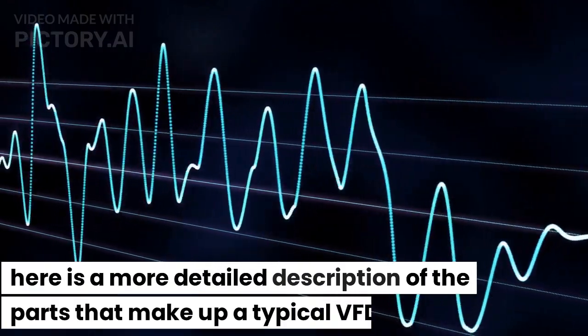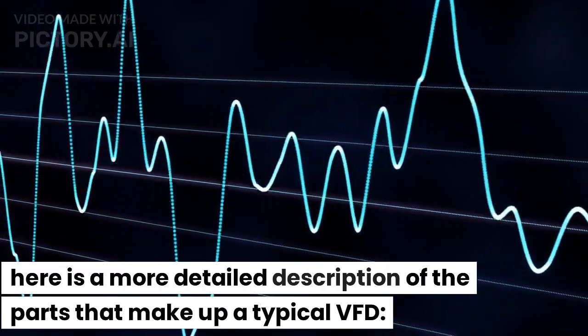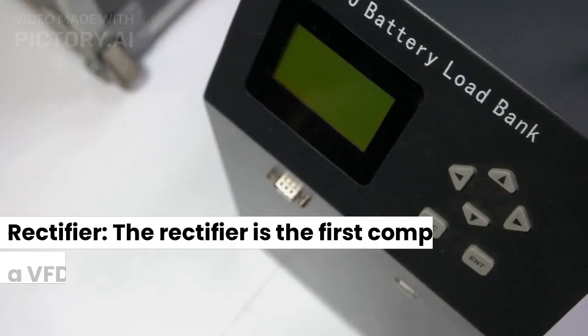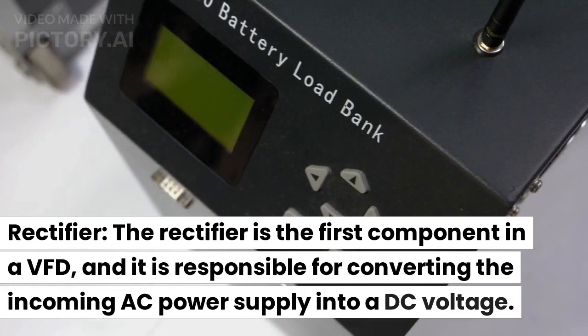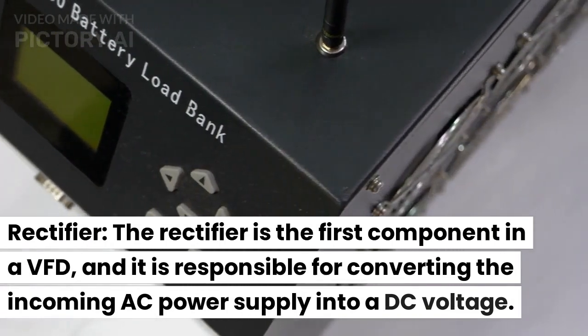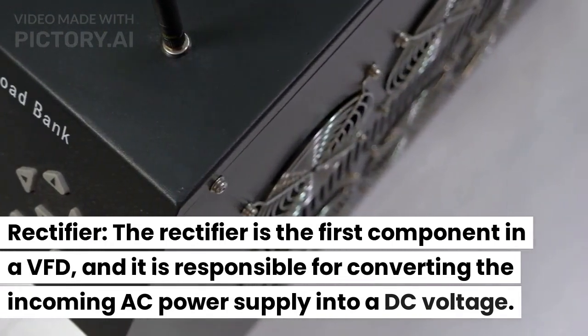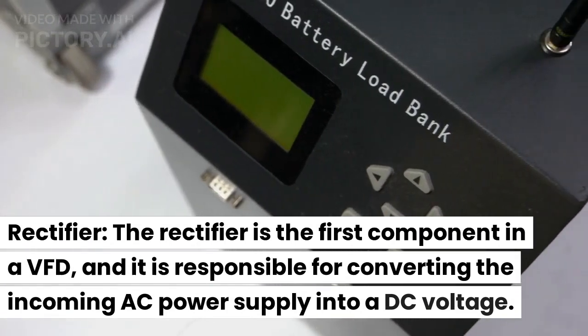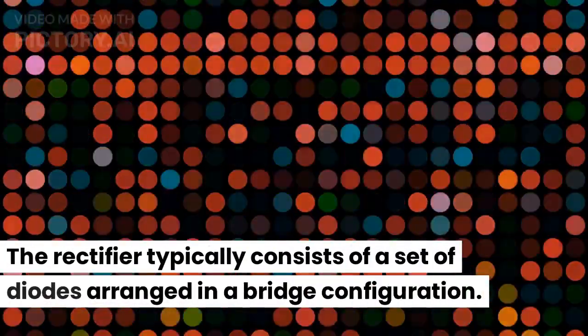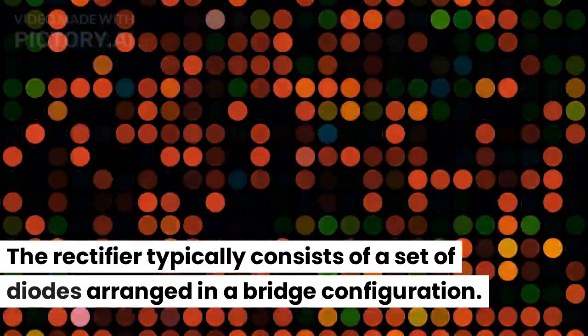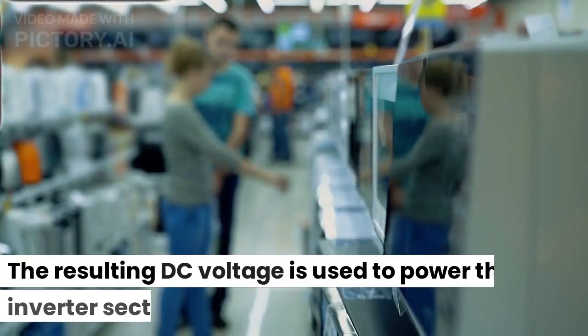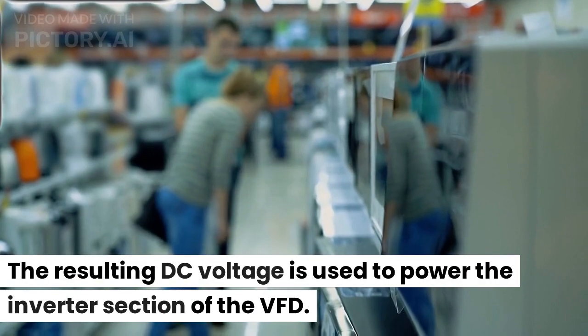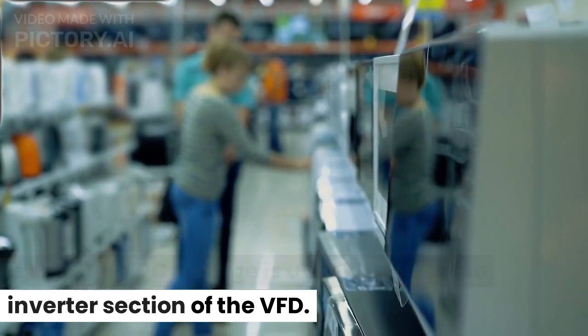Here is a more detailed description of the parts that make up a typical VFD. Rectifier. The rectifier is the first component in a VFD, and it is responsible for converting the incoming AC power supply into a DC voltage. The rectifier typically consists of a set of diodes arranged in a bridge configuration. The resulting DC voltage is used to power the inverter section of the VFD.